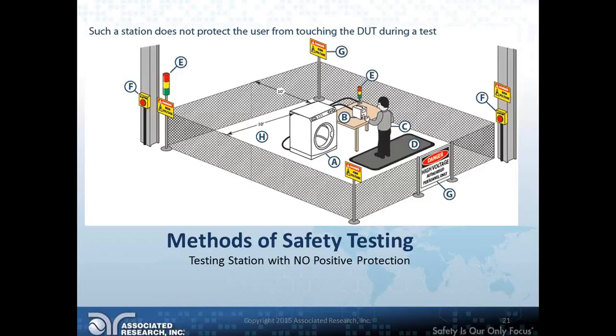Here you can see there's a gate up. Since there are exposed conductors, this station makes absolutely sure nobody walks in, because it's completely fenced off. This is a really good method I've seen a few people employ, because it's clear to anyone walking by: if you're not trained with that equipment, you're not going to go in there. So keep those two types of stations in mind, and ask yourself what you have and whether you're missing something—do we have the potential for a shock hazard because we're missing one of these things?